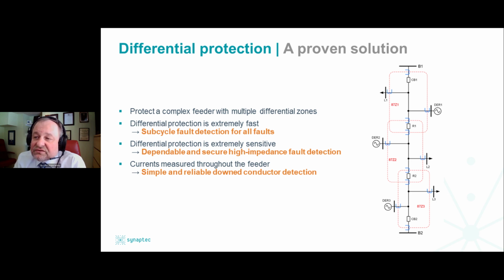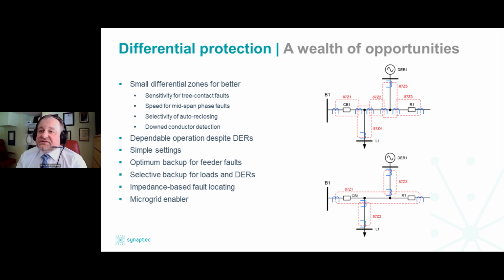And because you have those CTs throughout the feeder, you could provide better down conductor detection because you are closer to the problem, so to speak. So it's a wealth of opportunities. There is nothing really new on this slide. The bullets summarize the key advantages of differential protection. Differential protection has been practiced for many decades, close to a century, in transmission networks. We are all very familiar with this powerful principle.